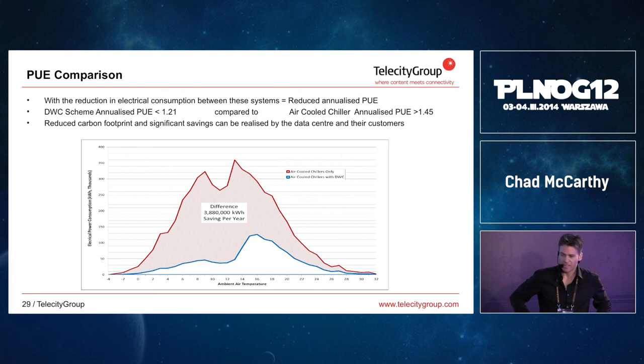So here we have an indication of how much energy we would be using with an air-cooled chiller system, which would look similar to the photographs I showed at the start of the presentation, where we have all this fairly intensive roof-mounted plant. We would have an annualized PUE in that condition of 1.45. And you can see the dock water scheme has an annualized PUE of 1.21. And that's indicated in the diagram with the red and the blue traces. So what's not really shown in the diagram is the cost of the dock water itself.